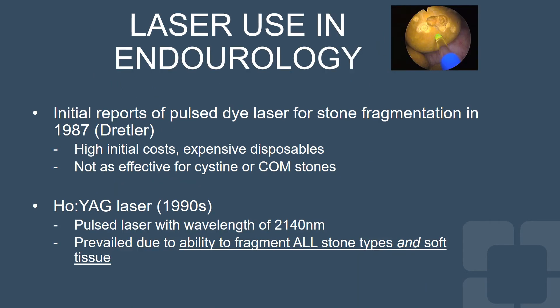Initial reports of pulsed dye laser for stone fragmentation occurred in 1987. However, these units faced high initial costs, expensive disposables, and they were not as effective for cysteine or calcium oxalate monohydrate stones, which are the denser stones. The holmium YAG laser was later introduced in the 1990s as a pulsed laser with wavelengths of about 2,000 nanometers, and prevailed due to its ability to fragment all stone types and also ablate soft tissue.